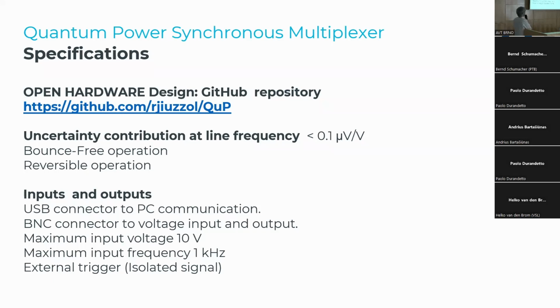The specifications to build the multiplexer are here: the uncertainty contributions should be less than 0.1 ppm at line frequency, bounce-free operation, and reversible operation. This means, as I'll explain later, the slave board has 2 inputs and 1 output, or 1 input and 2 outputs, so you can reverse the input or output as you want.